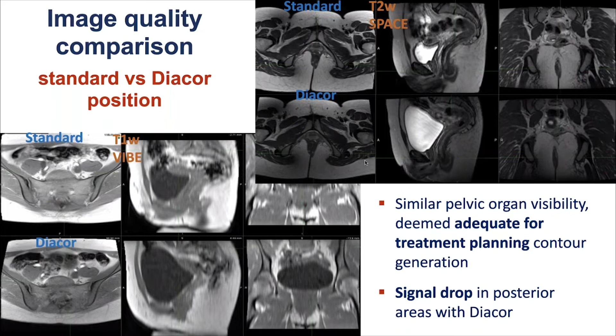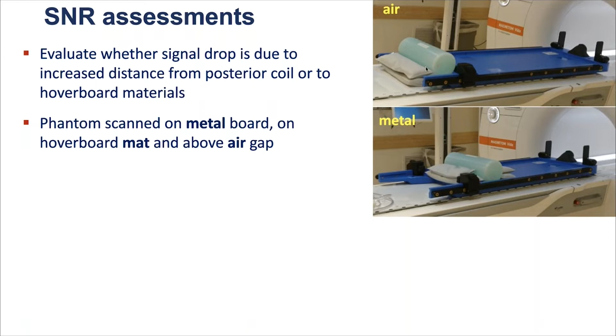To evaluate whether this signal drop was due to increased distance from the posterior coil or due to materials used in the hoverboard, we have performed phantom scans by placing the phantom either on a metal board or using a hoverboard mat in between, or placing the phantom in a position that we had an air gap underneath it.